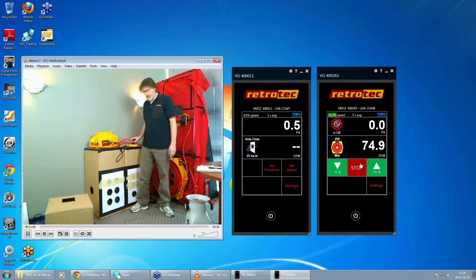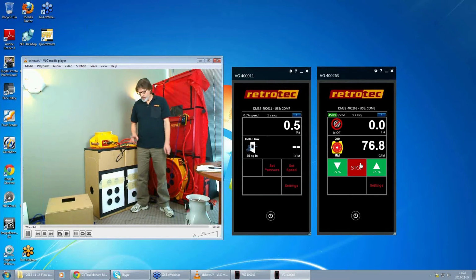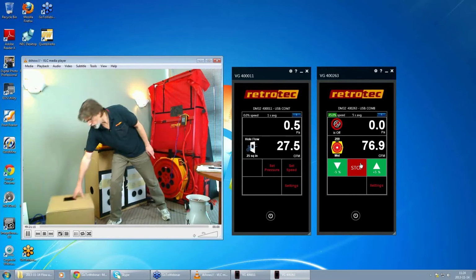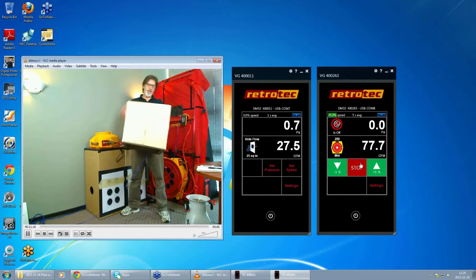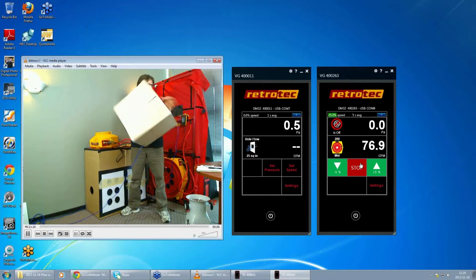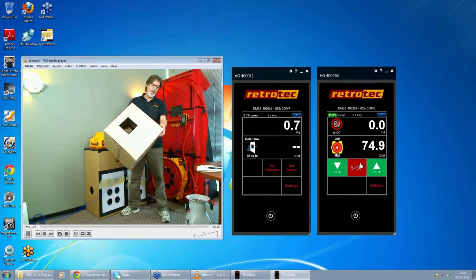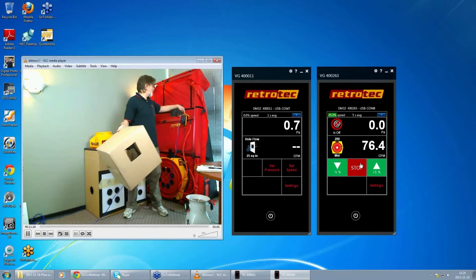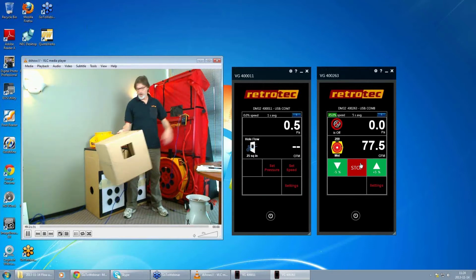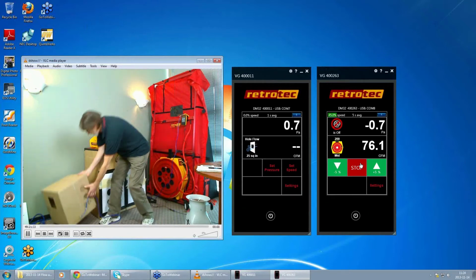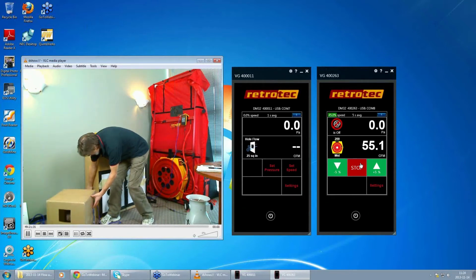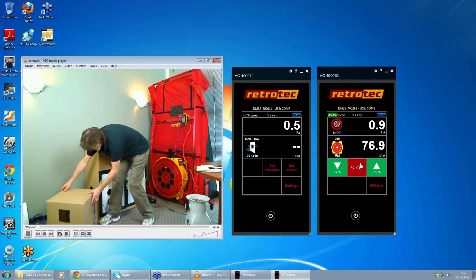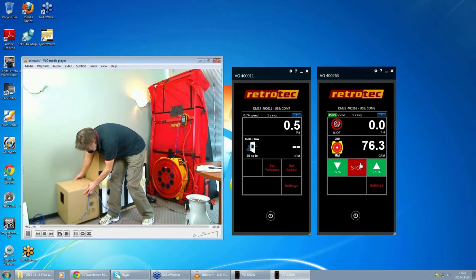So on the right-hand gauge, it says we're blowing 75 CFM. So what we're going to try and do is measure that 75 CFM with this elaborate apparatus here. So again, it's a box. It's got a 25 square inch hole in it. We've got a pressure probe here that goes all the way around and goes into the channel B of this particular gauge. And all we're going to do is set it up against this hole we have in the side, because this is the only hole we have in the system. The air is going into the hole, by the way.